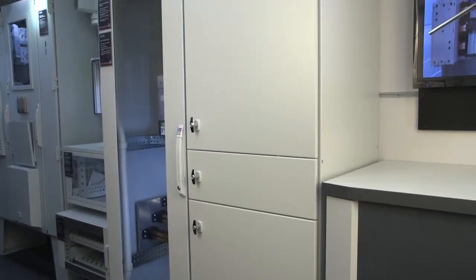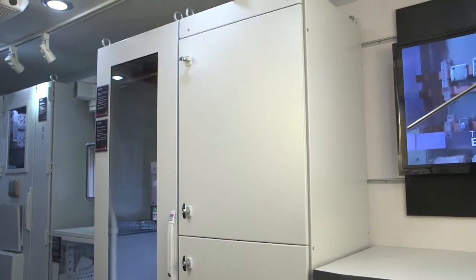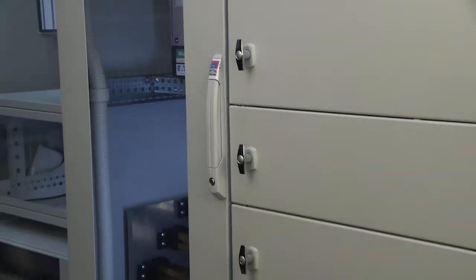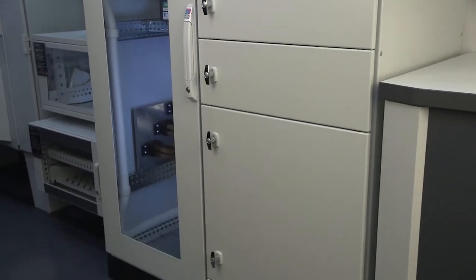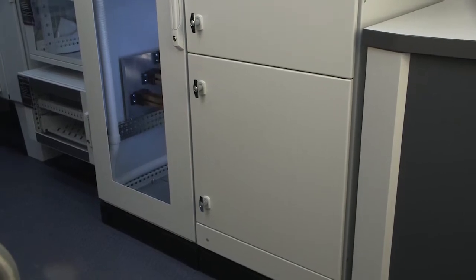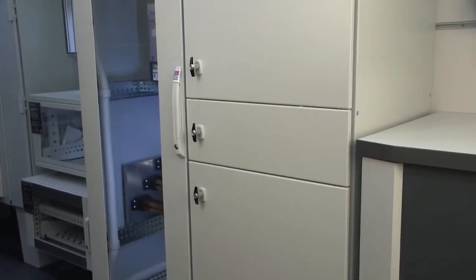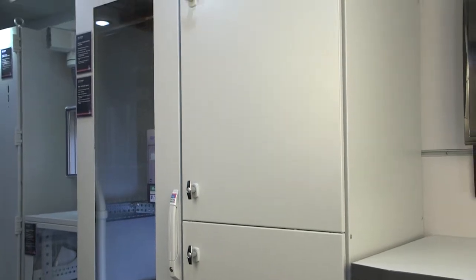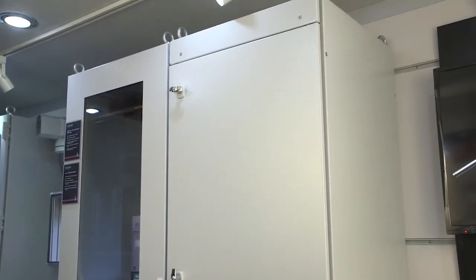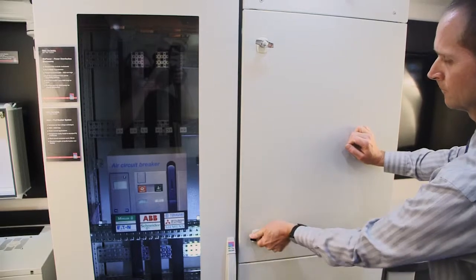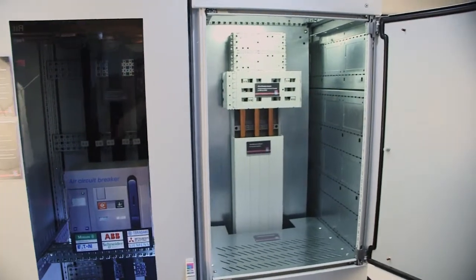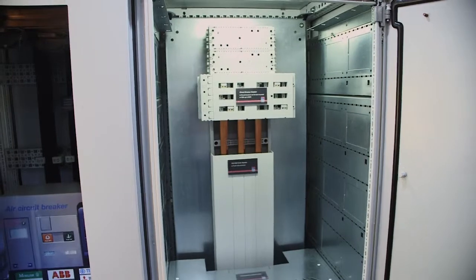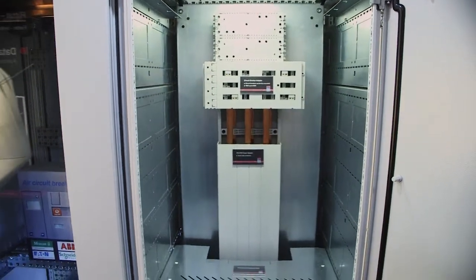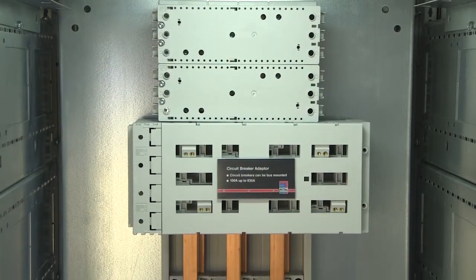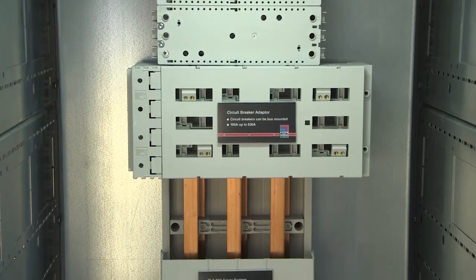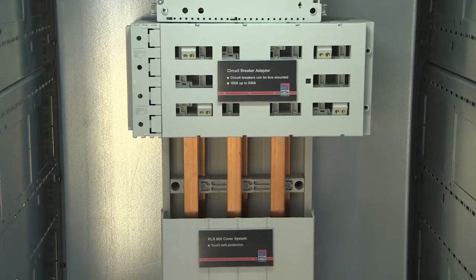The popular TS8 enclosure system remains unexcelled for flexibility and ruggedness, while delivering a clean, consistent environment under the most demanding conditions. This cabinet can be configured as a power distribution enclosure, providing isolation and compartmentalization for distribution equipment. Within this compartment, a PLS busbar system has been installed to distribute power to various components inside the enclosure. Among them are circuit breakers, which have capacities ranging from 100 to 630 amps.